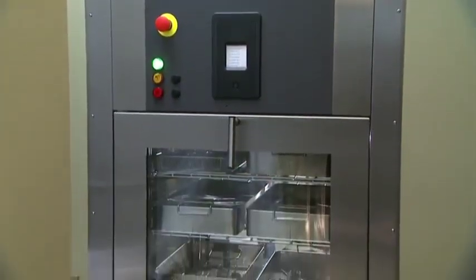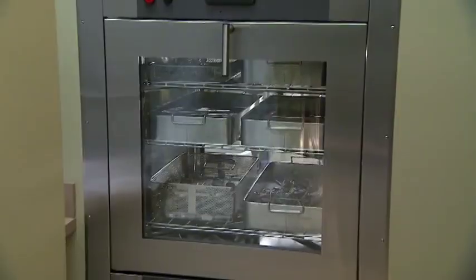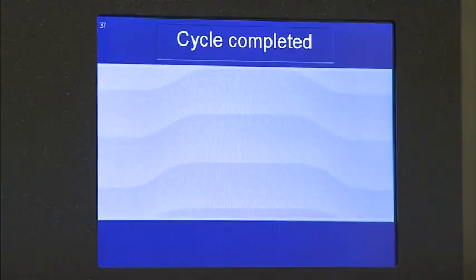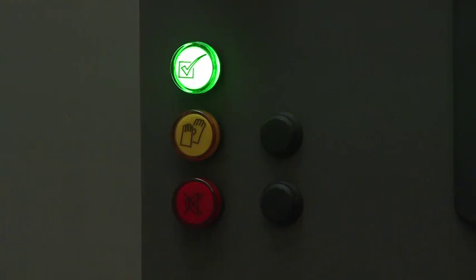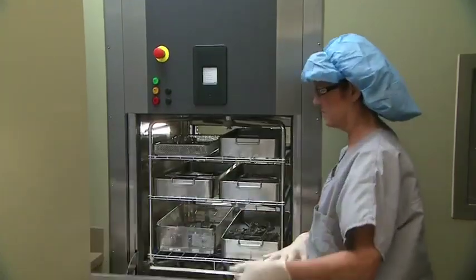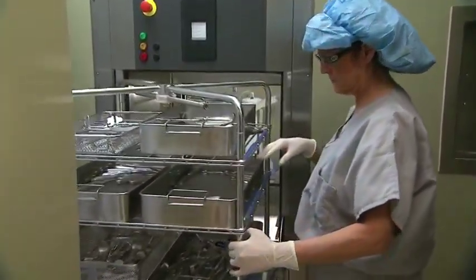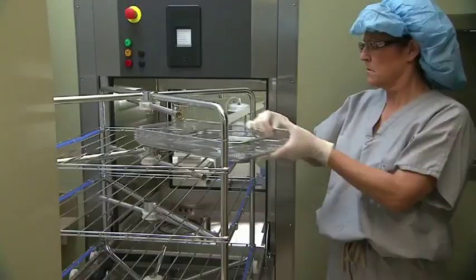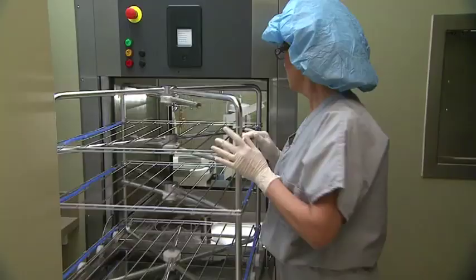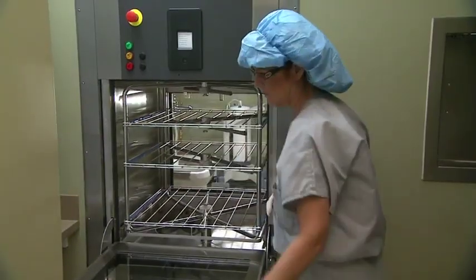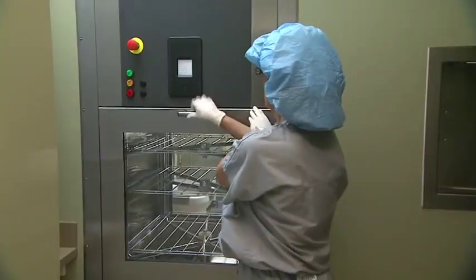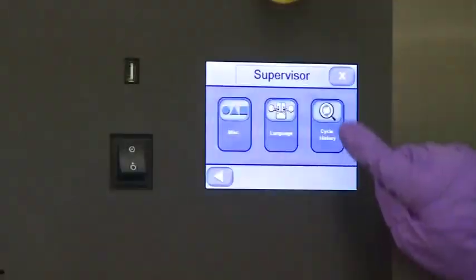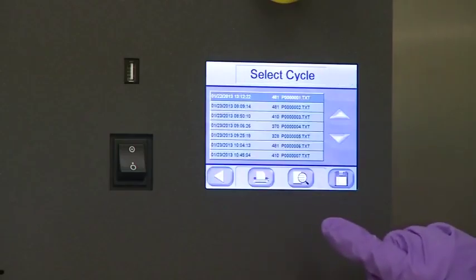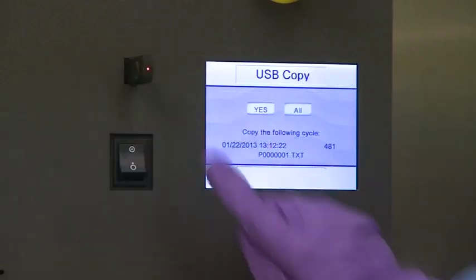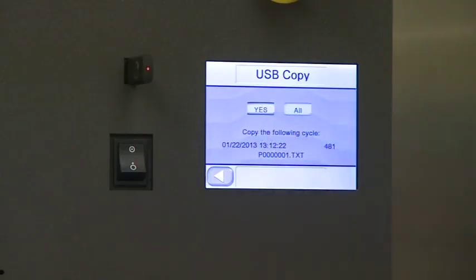Our cycle is now complete. It's time to unload the washer disinfector. Upon completion, a confirmation screen appears on the control screen and the Cycle Complete green indicator button illuminates. It's now safe to open the door. Carefully pull the manifold rack out of the chamber. When finished, roll the rack back inside the chamber and close the chamber load door. Be sure to turn the handle so it closes completely. And, with the USB electronic cycle download feature in the supervisor menu, it is easier than ever to collect cycle data and maintain a paperless work environment.